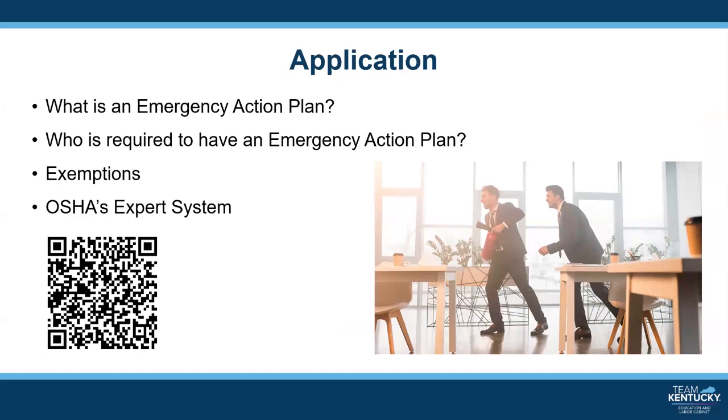Who's required to have an emergency action plan? Well, almost every business is required to have an emergency action plan, or an EAP. If fire extinguishers are required or provided in your workplace, and if anyone will be evacuating during a fire or other emergency, then OSHA's 1910.157, the standard for portable fire extinguishers, requires you to have an emergency action plan. The only exemption to this is if you have an in-house fire brigade in which every employee is trained and equipped to fight fires, and consequently, no one evacuates.